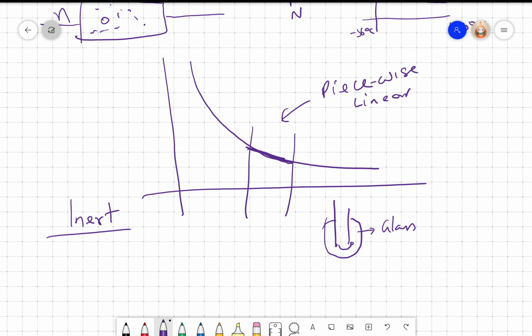Once I put glass around it, if I increase theta in a step fashion, the sensor would slowly rise, taking a few seconds, maybe 10 or 20 seconds, because we have to protect the PT100 with glass. So the dynamic response of RTD is quite bad.